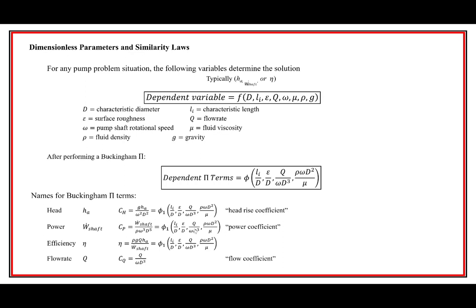Well, that remains true, but here quite often what we will do instead, if we have one pump of the same family, we could use the parameters from that pump to use another pump within that family and find out what a change to one of these parameters would be. Most often it's going to be impeller diameter or RPM, but it could be other aspects as well.